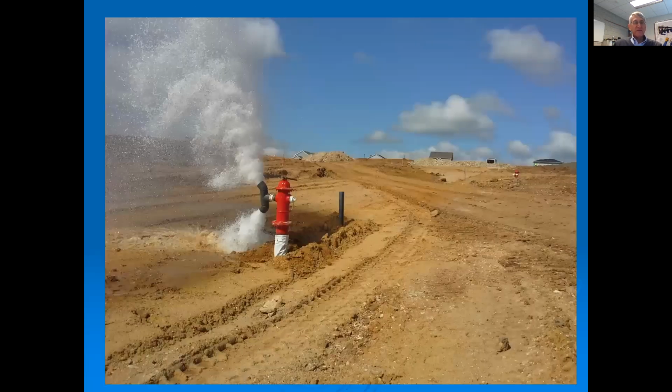Occasionally you may see us blowing off water on a newly constructed water main. That's a process that we have to go through in order to put a water main into service. So that water main has to be loaded, it's chlorinated, we test that to make sure there's no bacteria on it. Then we flush out that chlorine that we put in to disinfect that line before we put that into service and before we do our pressure testing.